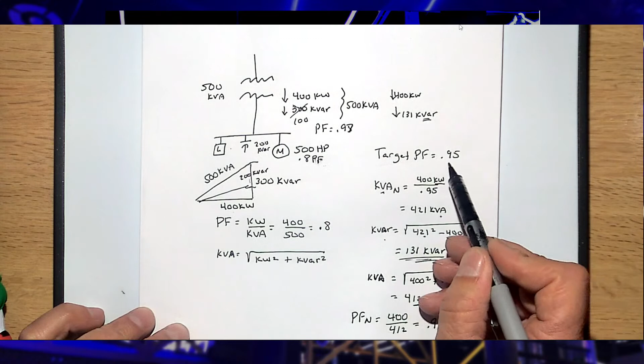Now, 131 kVAR is not the size of the capacitor. That's what's now flowing down through my system. What you have to think about for power factor correction is, how big is the capacitor that would give me 131 kVAR? The answer is 169 kVAR, which is not a standard capacitor. So in my example, I said you'd pick either a 150 or maybe a 200 kVAR, which might be a standard capacitor. If my target power factor is 0.95, I'm not going to pick a smaller capacitor that gives me less correction. I'm going to pick a bigger capacitor. So I put a 200 kVAR capacitor there.